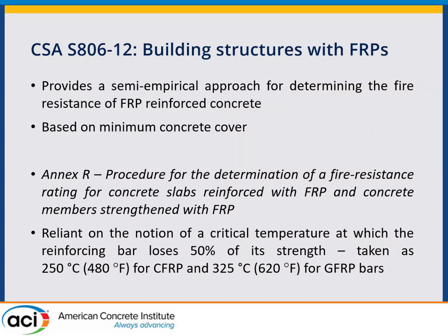Really this was put in because this is what's done for steel reinforced concrete: when steel reaches about 600 degrees Celsius, 1100 degrees Fahrenheit, it loses about half of its strength.